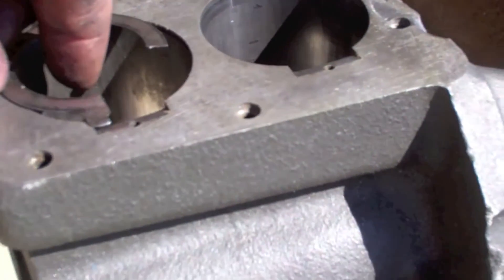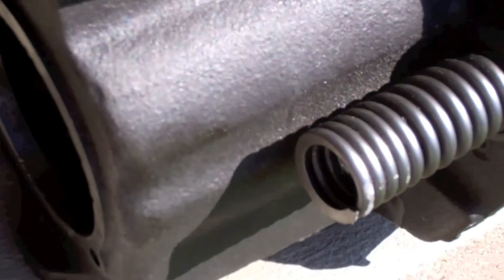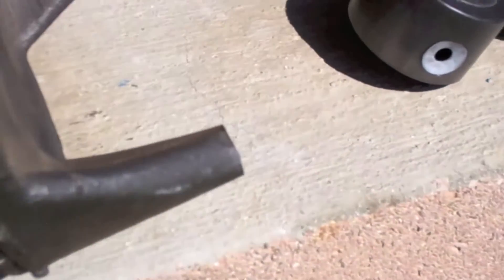Pay no attention to this, I did that with the hammer. But yeah, pretty bad shape. That's what happens when we get liquid coming back to the compressor. Even the bearing on the inside is in really bad shape. Scored.